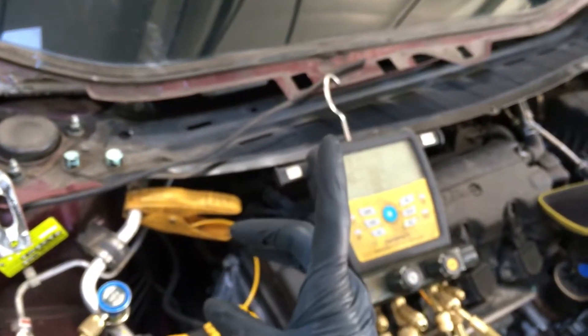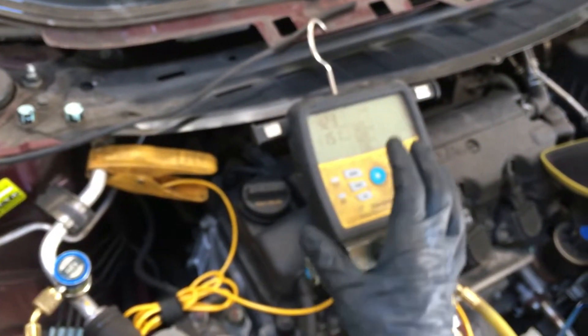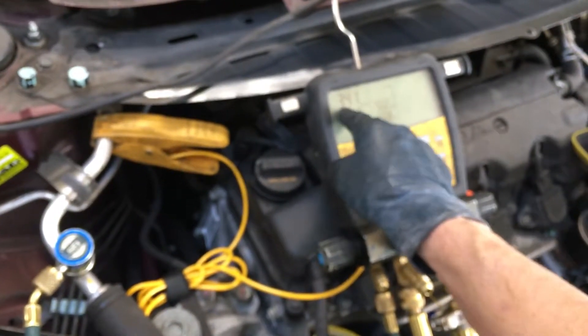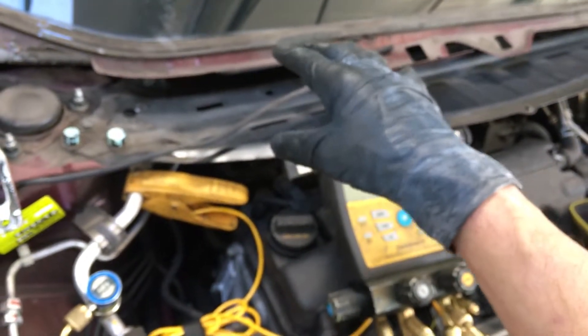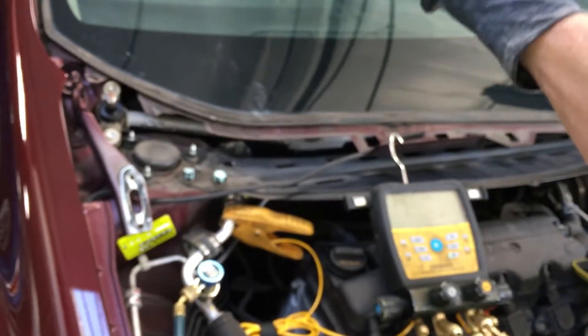There's this magic number they like to throw around — 500 microns. Five hundred microns is actually pretty sloppy. In old refrigeration days with analog needle gauges, somewhere around 200 microns is actually where you really want to go. Because of time pressure and cutting corners, they've raised the standard up to 500 microns. But reaching 500 microns doesn't mean much work has been done — stopping there and filling it up is not the right approach.